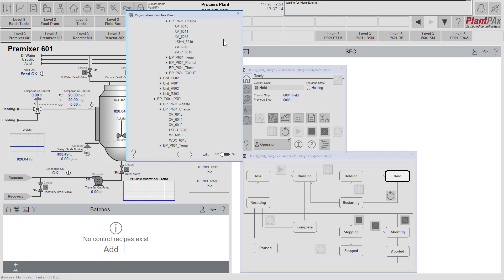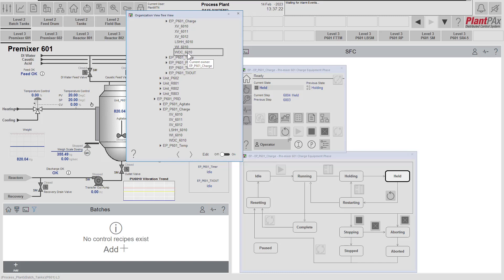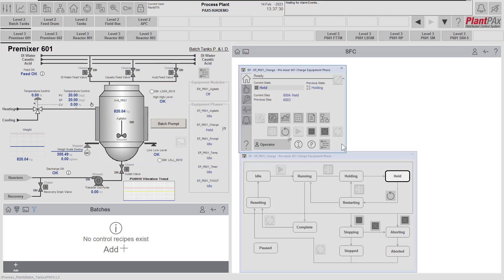The devices that are monitor-only and not controlled don't have ownership, so we can see here that ownership is not applicable to those devices. The dosing controller is controllable, so that is now shown as owned by our equipment phase. Having now successfully obtained all the devices this equipment phase needs, we can ask the equipment phase to restart, running through starting logic and going back into running. Let's do that from the faceplate.